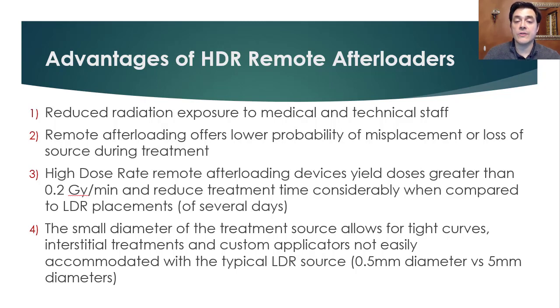Most of the time those procedures happen on an inpatient basis. So in addition to having the radiation oncology staff exposed, the medical staff of the supporting floor are often exposed. Number two, remote afterloading offers lower probability of misplacements or loss of the source during treatment. So for those that aren't familiar with it, oftentimes the manual afterloaders do not have any way to adjust where the source goes except for touching the source by itself or manhandling some sort of applicator or probe that is going to put the source in different places. The remote afterloader handles all the placement issues remotely or robotically, and the loss of a source during treatment is very unlikely as the source is welded onto a steel cable.